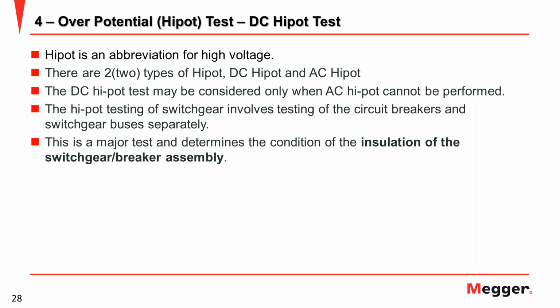DC hipot is also considered a basic test. Actually, this test checks the insulation performance of your breaker, like the insulation resistance test, but this is more specific, and you can be more confident when you do this hipot test. There are two types of hipot, DC and AC. AC is still preferred, and DC can only be done if you don't have an AC hipot. But the better way is AC for testing the hipot.